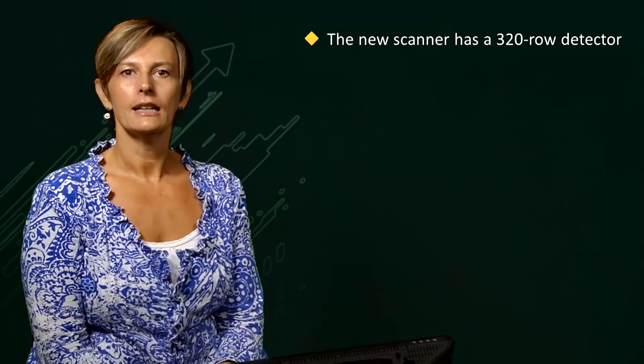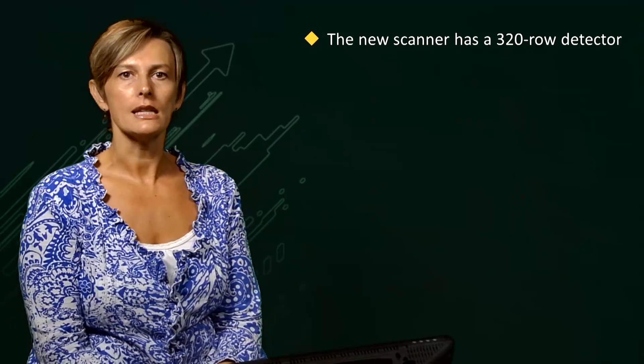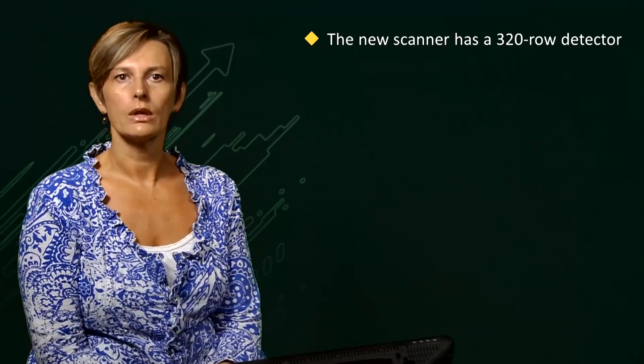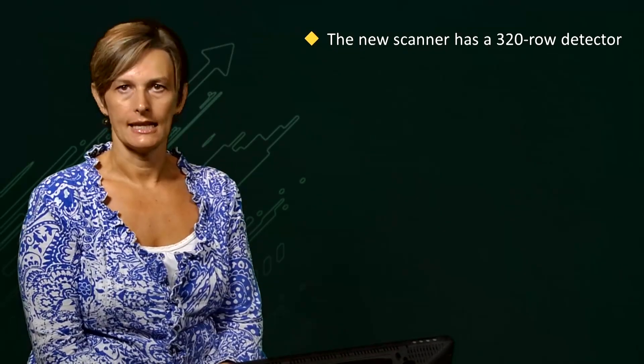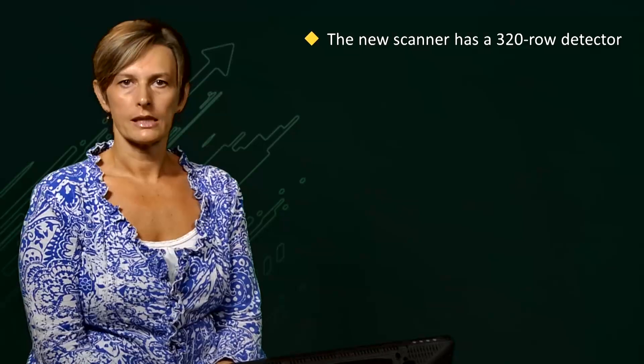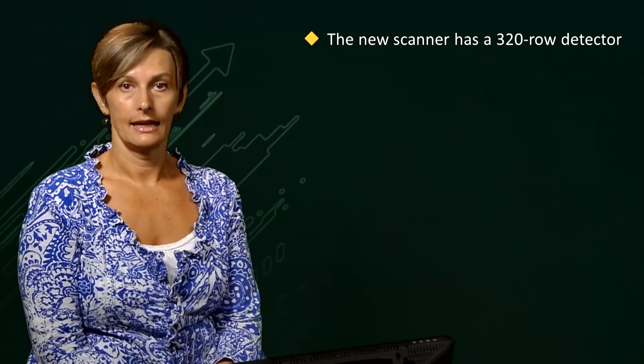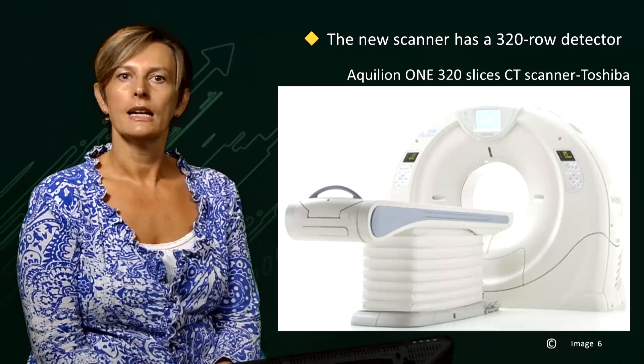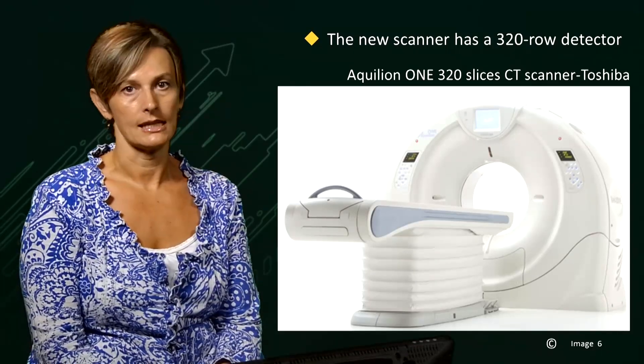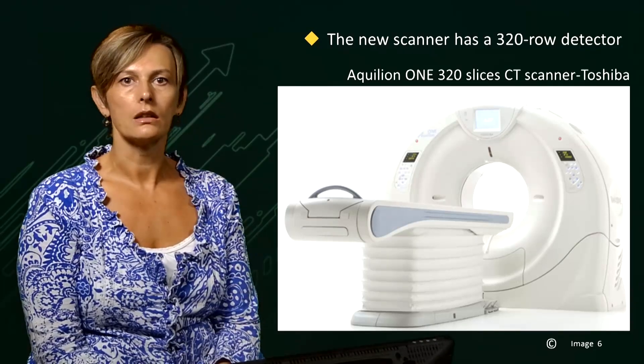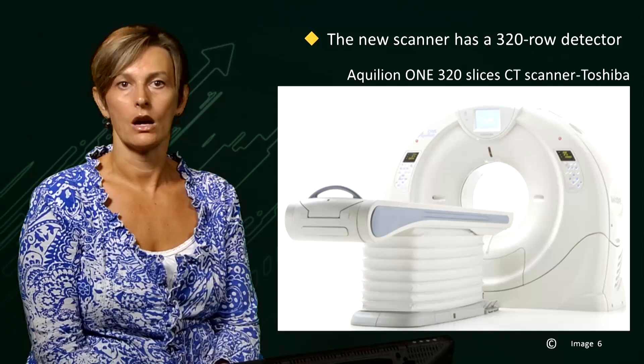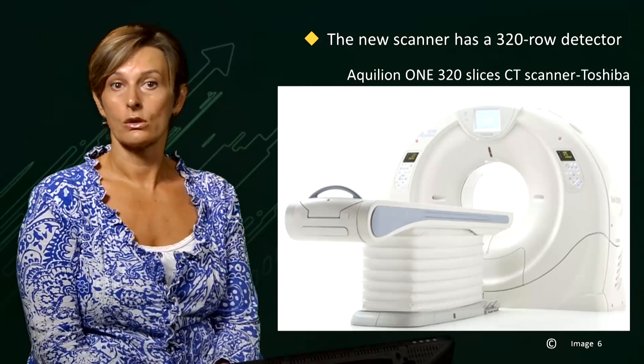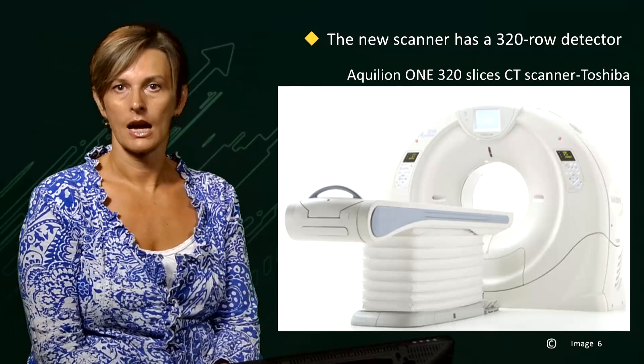If you are going for a CT scan, it is likely that you will be scanned with a CT scanner using 64 rows of X-ray detectors, also called 64-slice CT. However, newer scanners now have a 320-row detector, like this instrument. The Aquilion ONE is the world's first dynamic volume CT imaging system that enables acquiring entire organs with one volume scan, one rotation. Imaging a larger area of the body at one time is now possible, and scans take only 200 milliseconds.